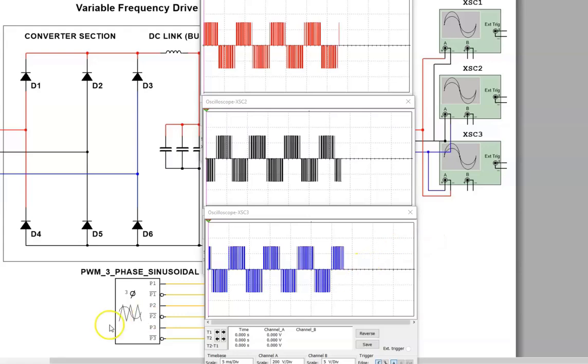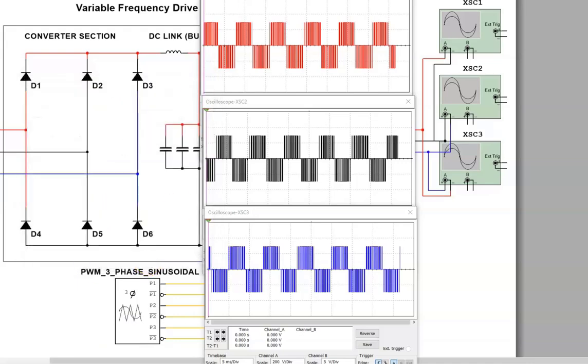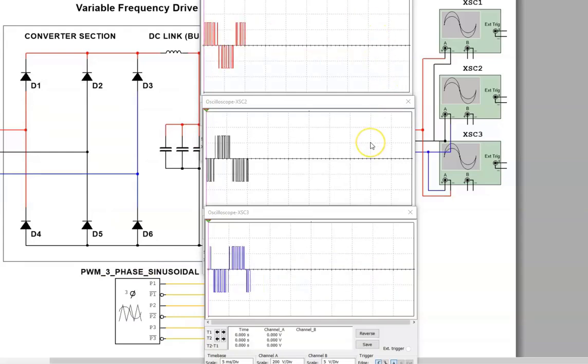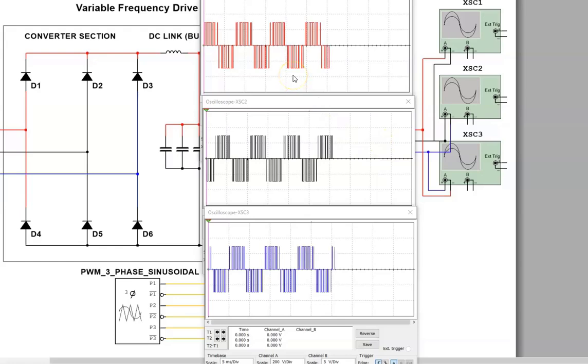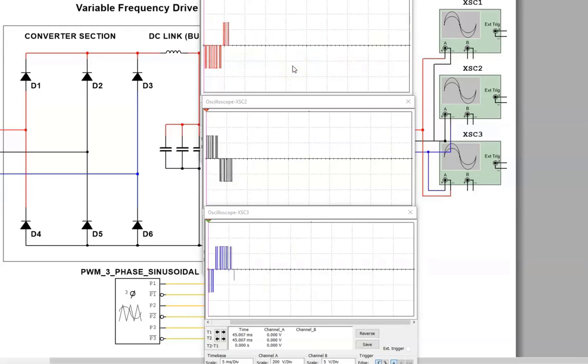One more thing we can do is we can adjust the carrier frequency. The carrier frequency will determine how many bars are produced to replicate that waveform. I'll take it down to 1 kilohertz. You might not see a big difference in that case. Now there's a slight difference. It's a lot easier on the motor. But you can certainly see the pulse width modulation that's used to recreate that AC waveform.